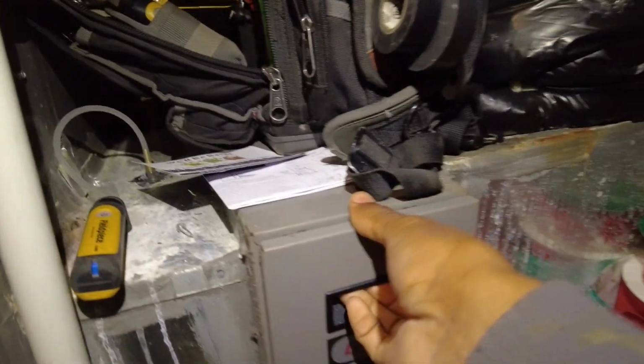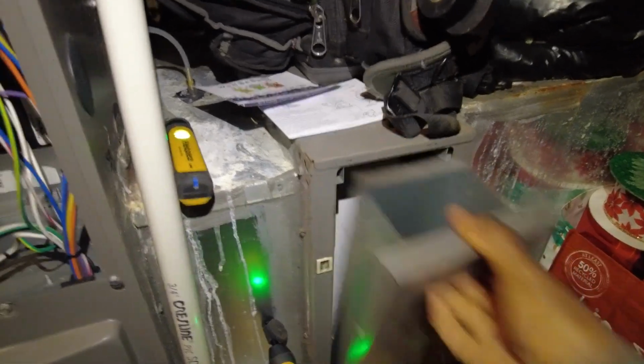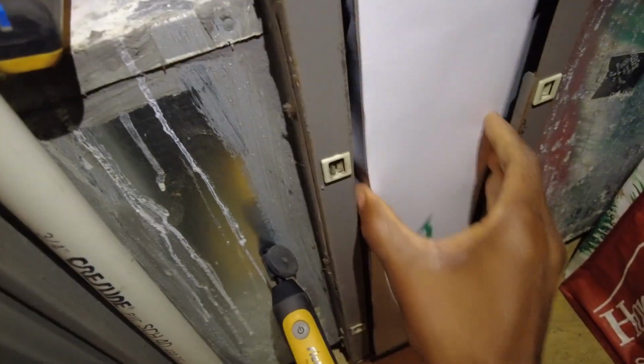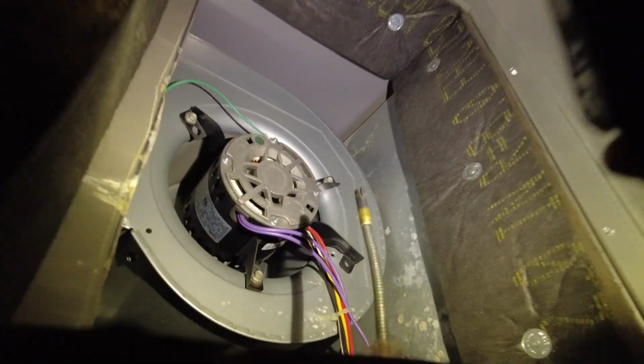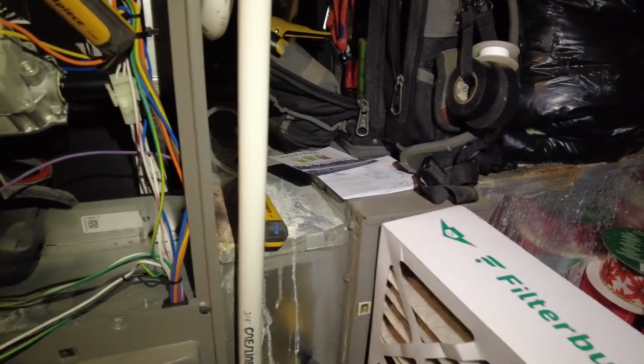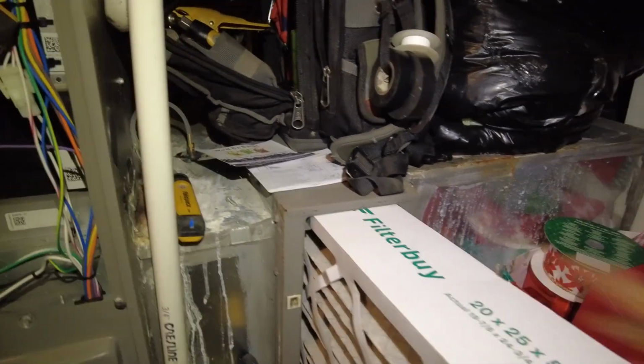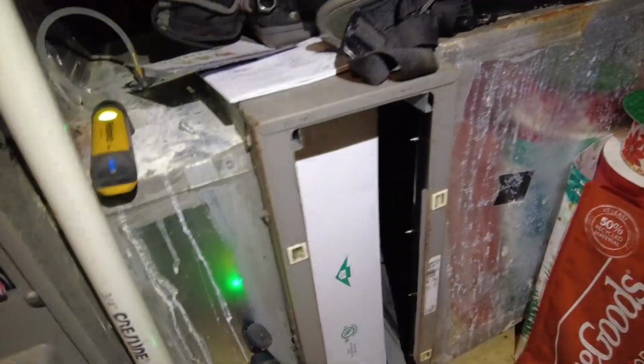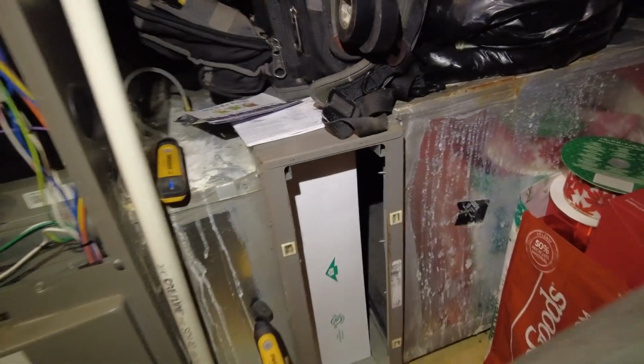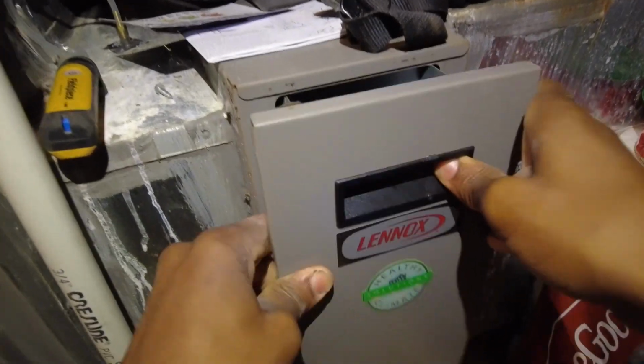Now, if you don't want to trust that, or if you don't have a meter, you can take your borescope, pull your filter, peek your head in there and see what's going on. There you go. There's your purple lines going up to the capacitor. You've got no module on the back of the motor, so it's a PSC motor. Okay, so that's a good thing.